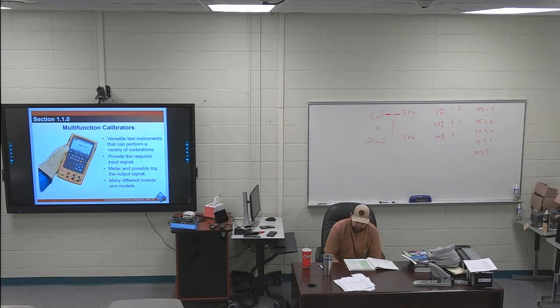Range and span, I think you'll probably do the highlights for those in the book, but those are good to know more than most everything else I've talked about. My first full highlight is the first sentence on the page. All instruments that provide a proportional output signal based on the input signal or level of energy must be accurately calibrated in order to function properly within the loop.